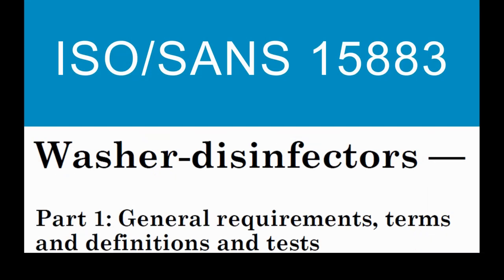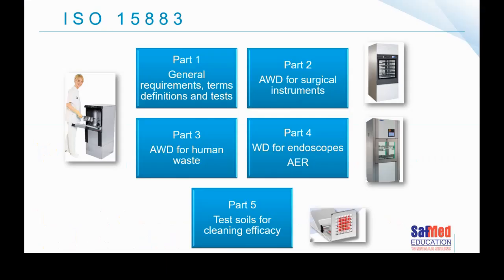ISO standard 15883 is one of my favourite standards personally. When I joined Safmed, I spent an entire week studying it. I was fascinated to understand that what we assume to be just a washer or a dishwasher is not just a dishwasher. The attention to detail and the parameters required in the manufacture of these devices are quite fascinating. ISO 15883 has five main parts, with additional parts being worked on. Part one covers general requirements — terms, definitions, and a variety of test methods. Part two is for specifically surgical instrumentation.